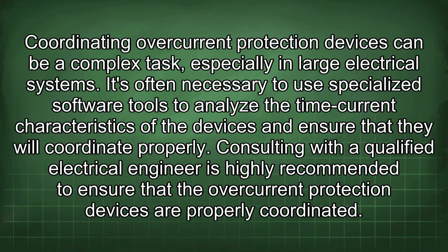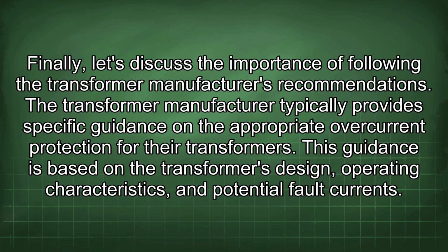Coordinating overcurrent protection devices can be a complex task, especially in large electrical systems. It's often necessary to use specialized software tools to analyze the time current characteristics of the devices and ensure that they will coordinate properly. Consulting with a qualified electrical engineer is highly recommended to ensure that the overcurrent protection devices are properly coordinated. Finally, let's discuss the importance of following the transformer manufacturer's recommendations.